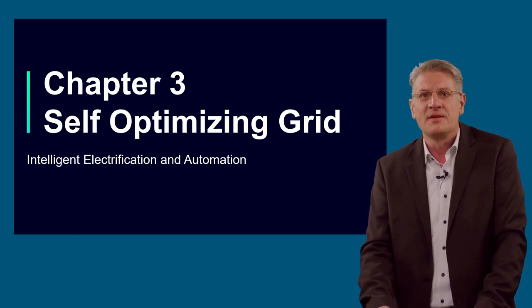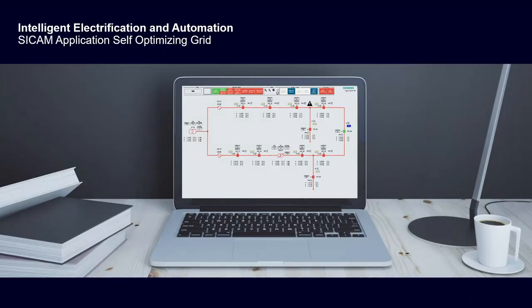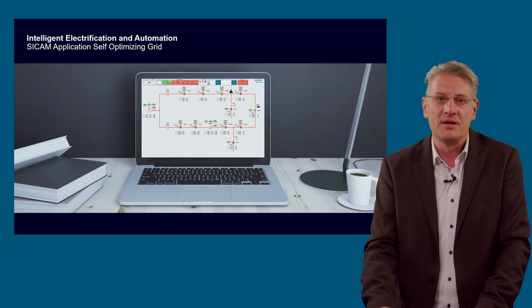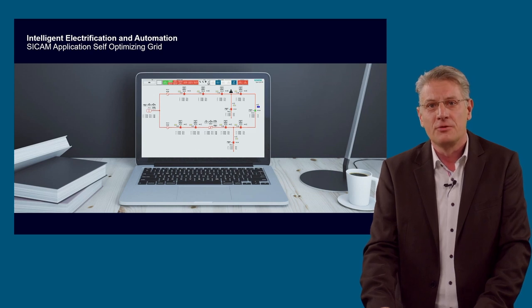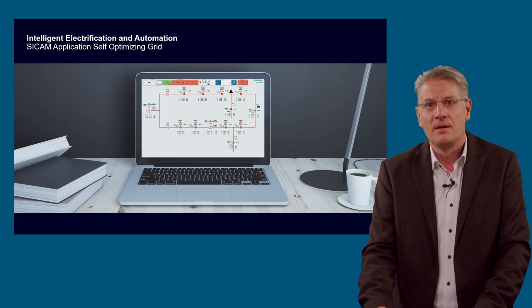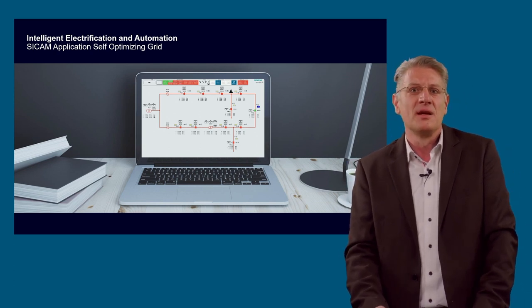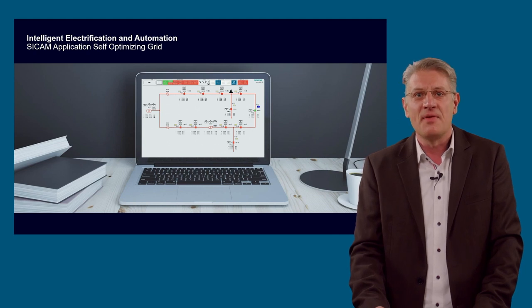Let's have a closer look at the self-optimizing grid application itself and how the system is implemented. Our application is based on our standard product portfolio and extends our automation system. The screen shows the human-machine interface of our SICAM application self-optimizing grid, which visualizes the state and enables the operator to take control of the self-healing system. The system works in a semi-centralized architecture where all relevant decisions are made on a regional controller. The main intention of the semi-decentralized approach is to create clusters in the network, meaning small areas can deploy closed-loop automation, with data from the field automatically processed and commands sent without human intervention.